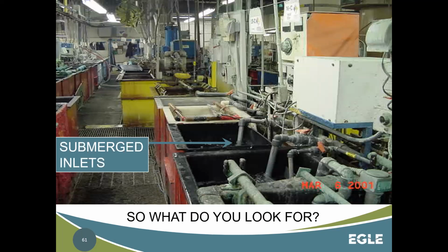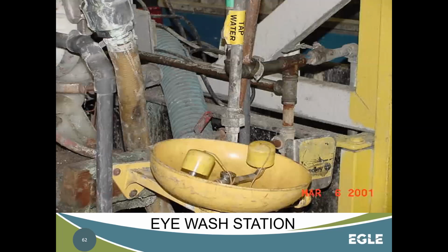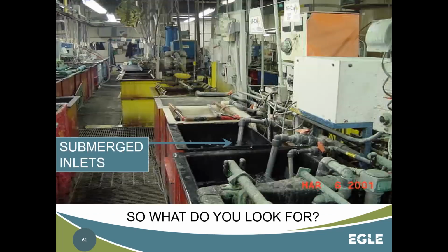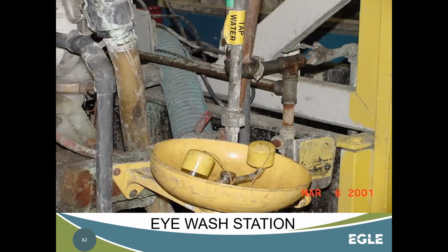So this one, we've got this whole series of different tubs and sinks. We've got a whole bunch of submerged inlets that are in place. And what turned out on this one is this eye wash station was actually plumbed off that same section of plumbing. So what could happen in a backflow event is whatever is being held in these tubs could actually get pulled back into the plumbing and then would be coming out of this eye wash station, which really is defeating the purpose of the eye wash and could create a very direct and obvious health hazard.